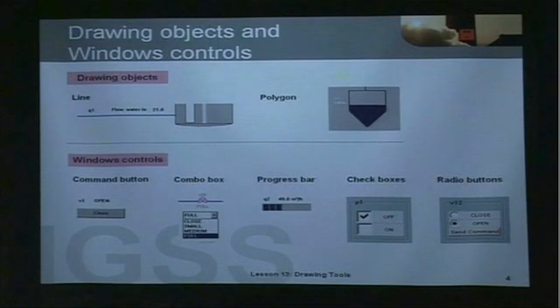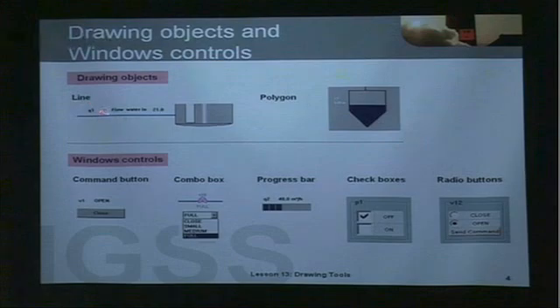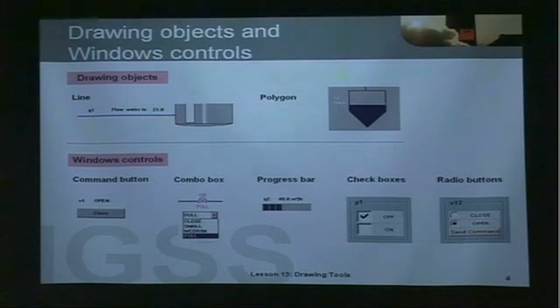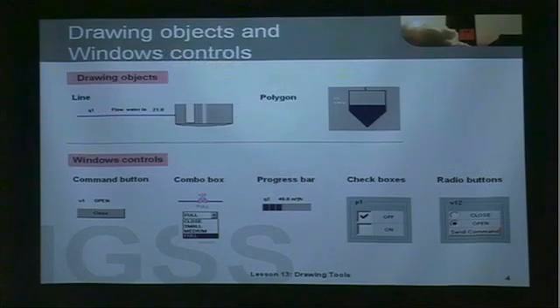What can you use this for? For example, if you have a flow meter Q1, you could connect this flow meter to a line in IGSS. You simply draw the line in IGSS and connect it to the object Q1. Then the line will reflect the process value of Q1 — if it's in alarm, for example, you can make the line blink. Right now it's just in the normal value section. Over here we have a polygon, which is exactly what you're going to be doing in the exercise that follows this presentation.